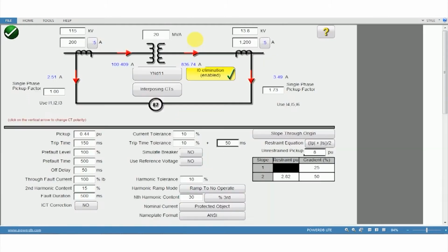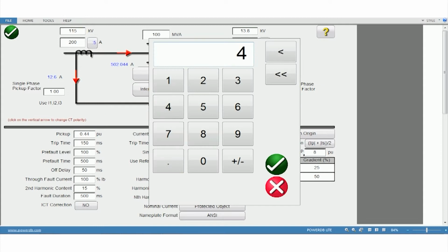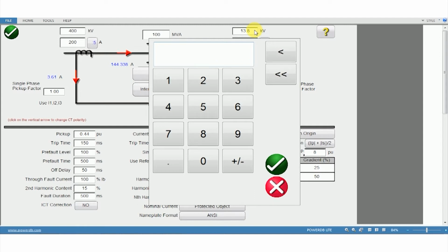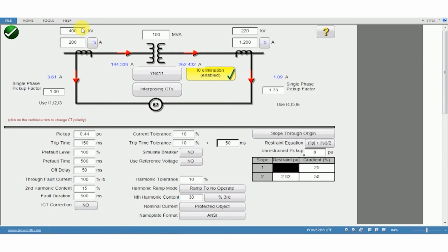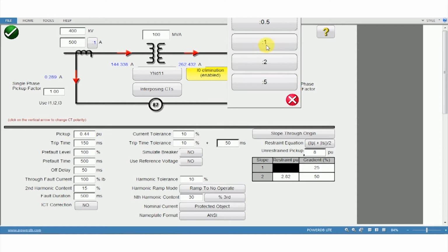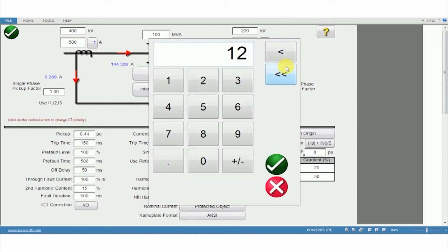To do this, click on the window and you'll get an option like this. You'll see a line, and on top of it, you need to enter the nameplate details of your transformer, such as MVA rating, the HV and the LV. For example, 400 kV by 220 kV transformer, and 100 MVA. Based on the voltage and the MVA, I get the full load current.